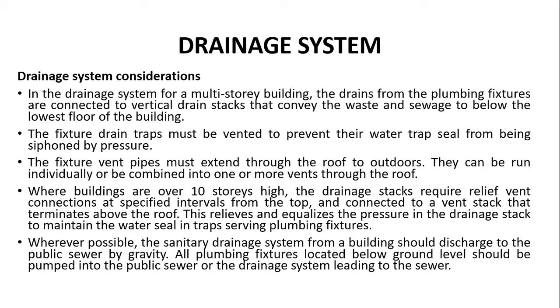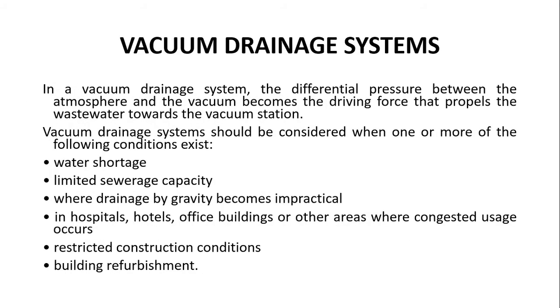If a building is over 10 stories high, the drainage stack requires a relief vent connected at specific intervals and connected to a vent stack that terminates above the roof. This relieves and equalizes the pressure in the drainage stack to maintain the water-seal traps serving plumbing fixtures. Ideally, sanitary drainage from a multi-dwelling or multi-story building should discharge to the public sewer by gravity. If the building has a basement with plumbing fixtures below ground level, a pump should be installed to carry the waste material from the fixtures to the public sewer. Mostly we use vacuum drainage systems in multi-story buildings.